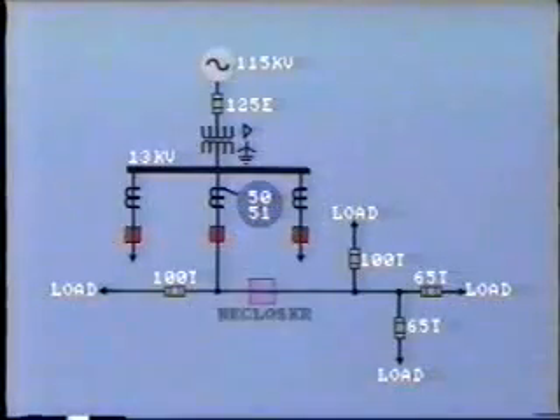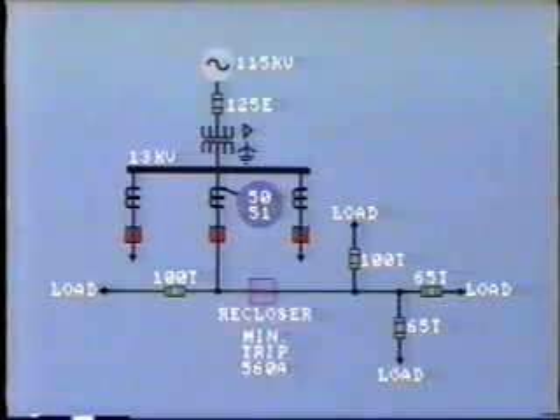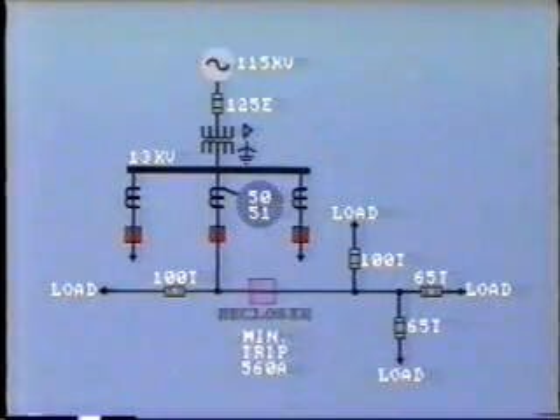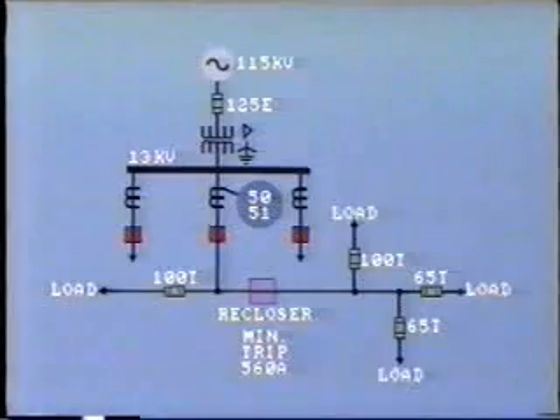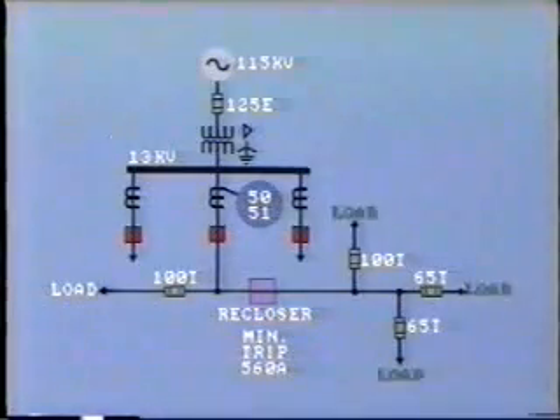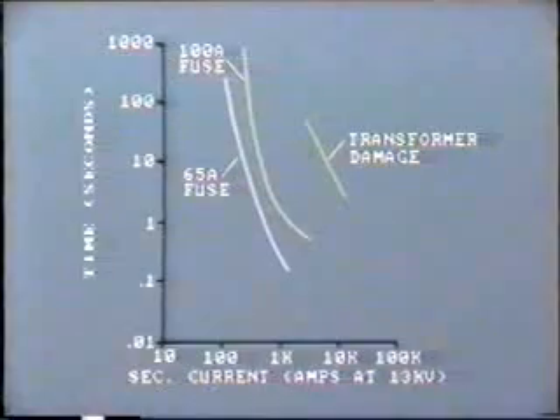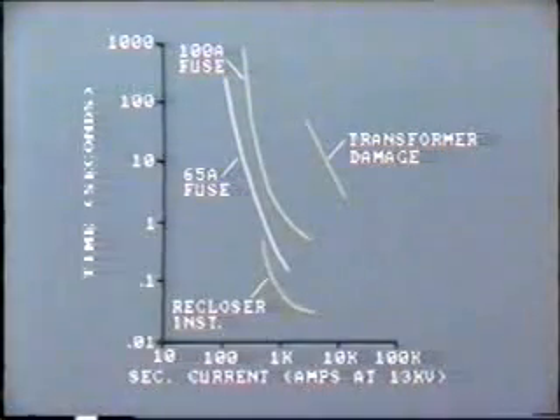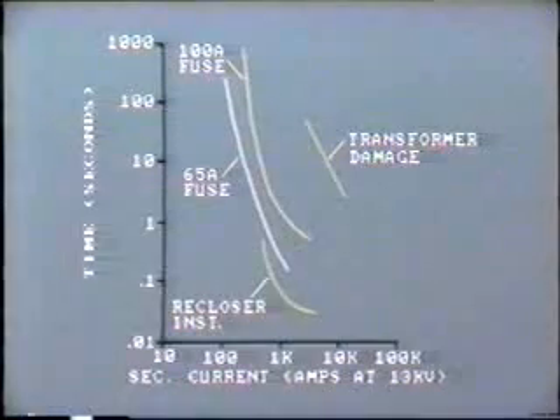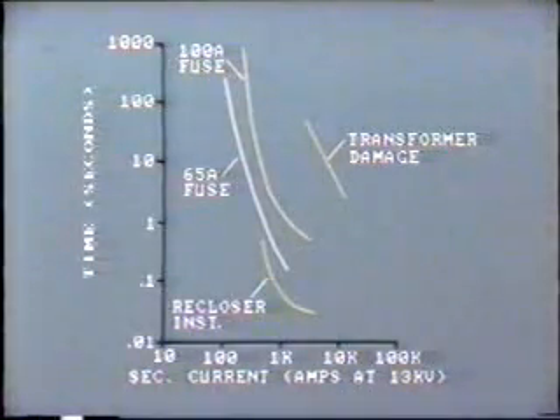Let's take a look at the recloser. The minimum trip rating phase fault is set at 560 amps. This is just over twice the normal load current at this point. The first trip, that is instantaneous, will trip before the downstream fuse has time to operate if current is above pickup. It will reclose again and wait for the second trip, which is time delayed.